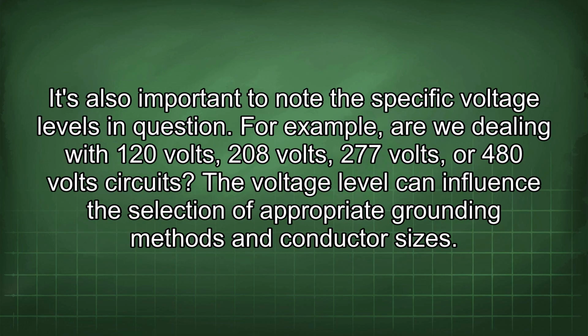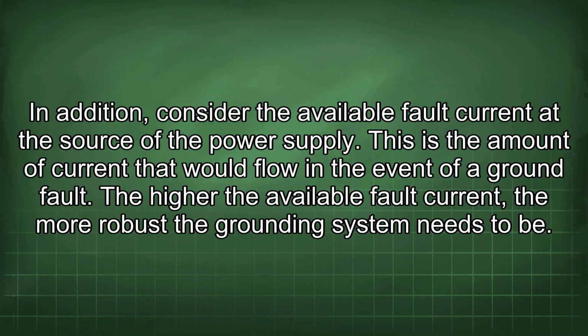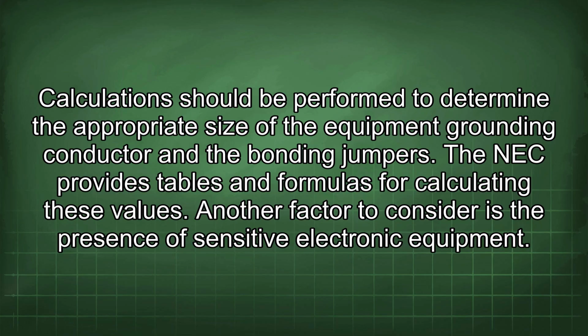It's also important to note the specific voltage levels in question. For example, are we dealing with 120 volts, 208 volts, 277 volts, or 480 volt circuits? The voltage level can influence the selection of appropriate grounding methods and conductor sizes. In addition, consider the available fault current at the source of the power supply. This is the amount of current that would flow in the event of a ground fault. The higher the available fault current, the more robust the grounding system needs to be. Calculations should be performed to determine the appropriate size of the equipment grounding conductor and the bonding jumpers. The NEC provides tables and formulas for calculating these values.